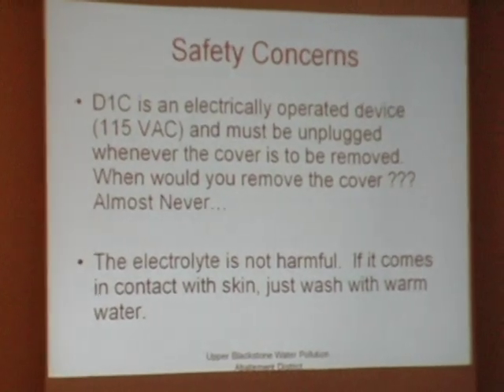The sensor works on the principle of an electrolyte, which is placed inside a membrane cap, and it allows the transmittal of that current from the outside to the inside. The electrolyte is a very viscous, thick material. If you thought honey was thick, this has got it beat by a mile, all right? But it's extremely safe. Don't worry about it. Get it on your hands, just wash it off with warm water. It's really non-toxic in that sense.